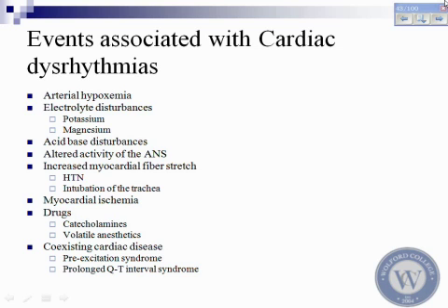Their operating rooms were under new construction, and somebody had connected the nitrous oxide to the oxygen line. So when they saw the saturation begin to fall, they immediately shut off what they thought was nitrous oxide and bumped up the oxygen. What they were doing was converting the patient from a little bit of oxygen to 0 oxygen with 100% nitrous oxide, and all 3 people died.